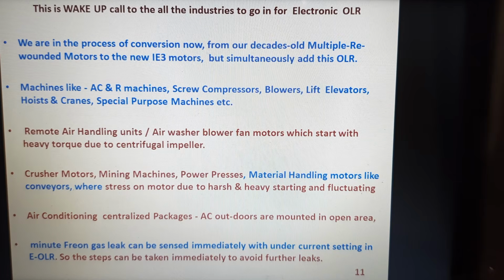The air conditioning centralized packages, and also the AC outdoors or the AC compressors, need the electronic motor protection relay and the pump protection relay, which has an undercurrent setting also. In case of any minute freon gas leaking in the outdoor, it automatically gives an alarm and can trip the outdoor and protect your air conditioning system.